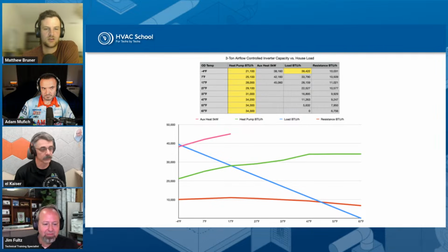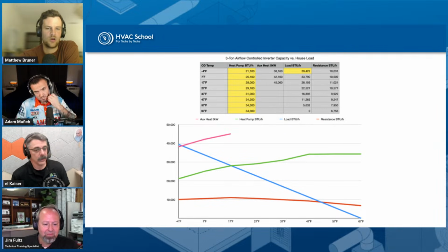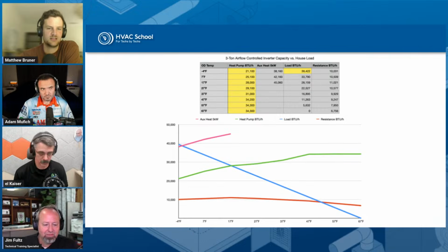So a COP of 1 would be where the green line and the red line met. When they meet, that's your COP of 1. So why would I shut that heat pump off? Because I'm still getting less expensive heat. I can't heat the house 100%, and I shouldn't be. Okay, yes, this is air to air. Great question.